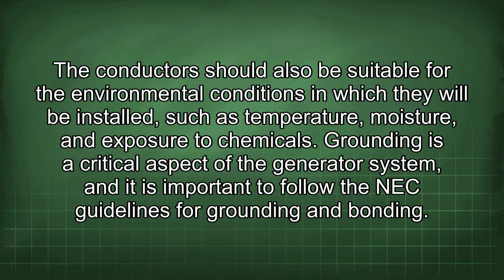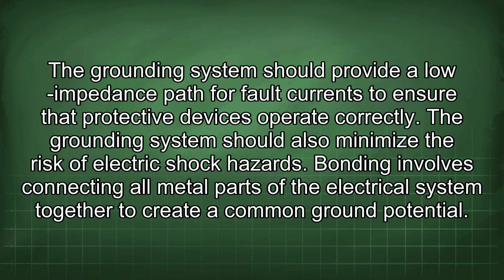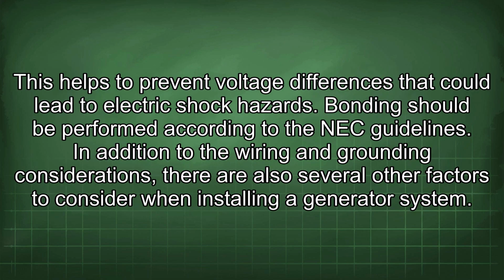and exposure to chemicals. Grounding is a critical aspect of the generator system, and it is important to follow the NEC guidelines for grounding and bonding. The grounding system should provide a low impedance path for fault currents to ensure that protective devices operate correctly. The grounding system should also minimize the risk of electric shock hazards. Bonding involves connecting all metal parts of the electrical system together to create a common ground potential. This helps to prevent voltage differences that could lead to electric shock hazards. Bonding should be performed according to the NEC guidelines.